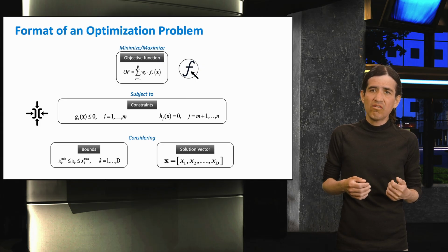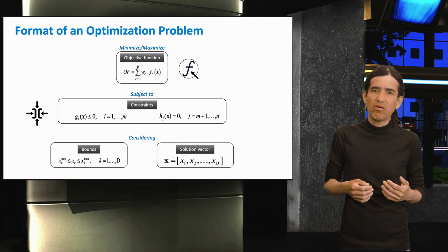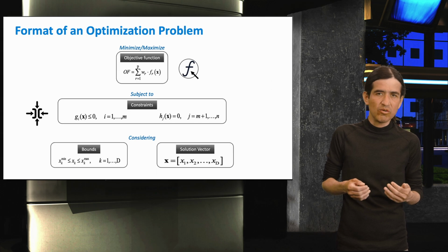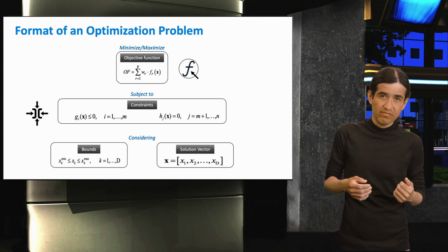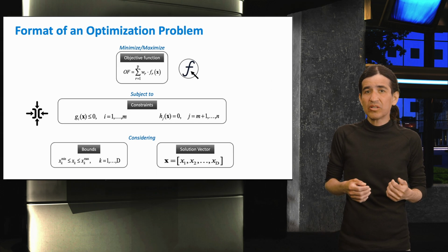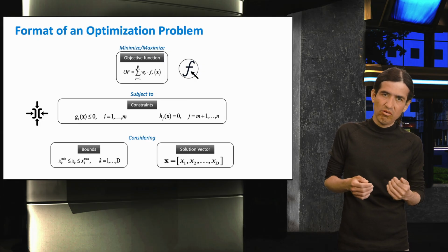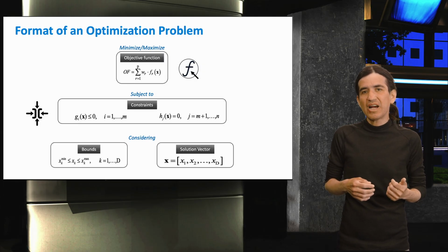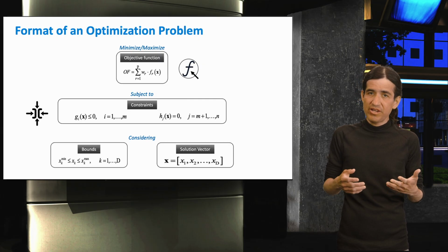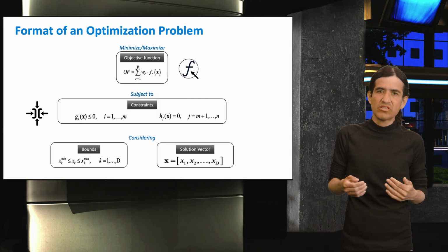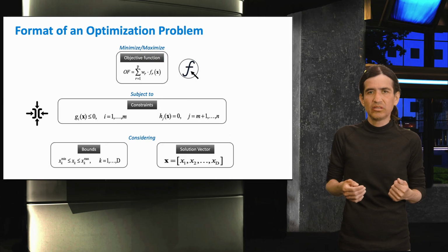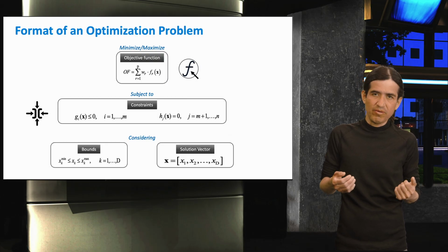For instance, if one of our variables is setting the output power of a certain generator in the network, then it is easy. The maximum and minimum possible outputs of any sort of generator is a well-documented value. Now, of course, you probably cannot operate this generator at the limits when it is in a certain network, for instance, because of thermal constraints of the cables in that zone. This is the technical constraints part.